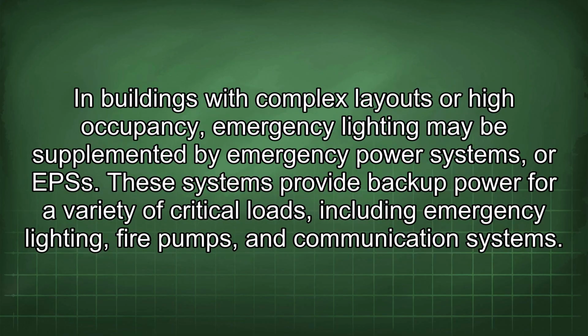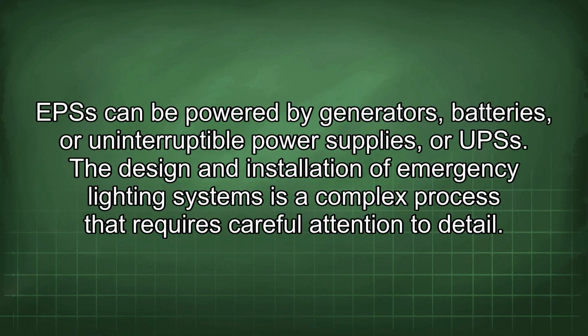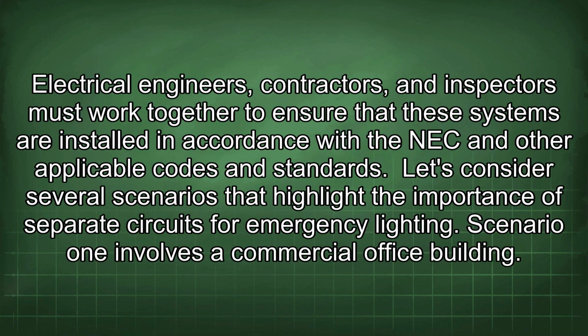In buildings with complex layouts or high occupancy, emergency lighting may be supplemented by emergency power systems, or EPSs. These systems provide backup power for a variety of critical loads, including emergency lighting, fire pumps, and communication systems. EPS can be powered by generators, batteries, or uninterruptible power supplies, or UPSs. The design and installation of emergency lighting systems is a complex process that requires careful attention to detail. Electrical engineers, contractors, and inspectors must work together to ensure that these systems are installed in accordance with the NEC and other applicable codes and standards.